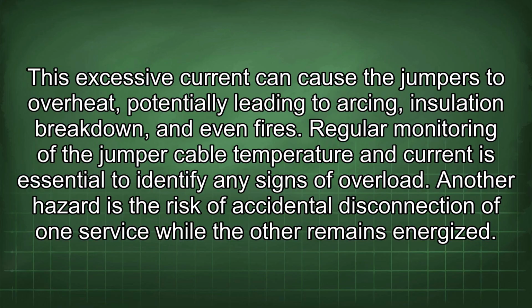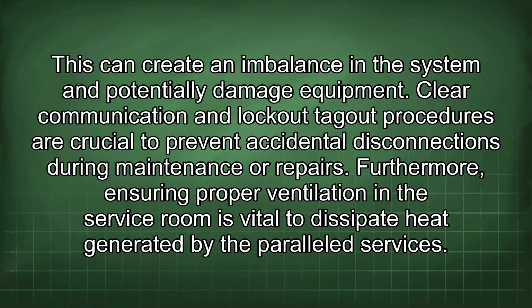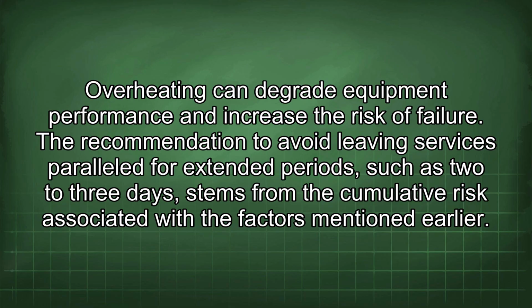Another hazard is the risk of accidental disconnection of one service while the other remains energized. This can create an imbalance in the system and potentially damage equipment. Clear communication and lockout-tagout procedures are crucial to prevent accidental disconnections during maintenance or repairs. Furthermore, ensuring proper ventilation in the service room is vital to dissipate heat generated by the paralleled services. Overheating can degrade equipment performance and increase the risk of failure.